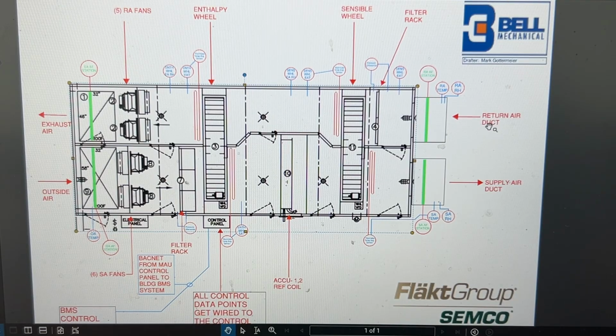And the return air duct that comes back through will pass through the filter bank, your sensible wheel, your enthalpy wheel, your return air fans, and then it's exhausted out to atmosphere here.